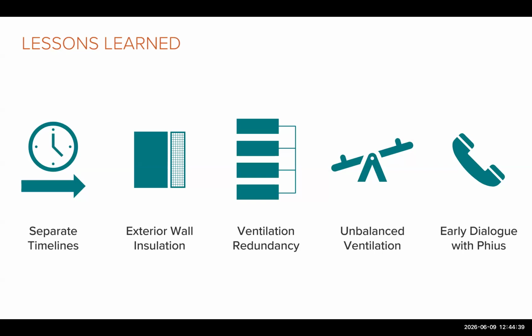As Kristen mentioned, ventilation redundancy is essential in medical office buildings. Originally, we wanted one ERV per floor, a very simple way of reducing ventilation flow rates after hours. This allows the building to remain balanced. However, this would have risked full floor impact if one of the ERVs is down and needs to be serviced. So instead, for resiliency, we have all ERVs connected to every floor and use the dampers, as Kristen mentioned, to turn down the ventilation 50% after hours. So there's a bit of push and pull of balancing these things when we're looking at all these factors.